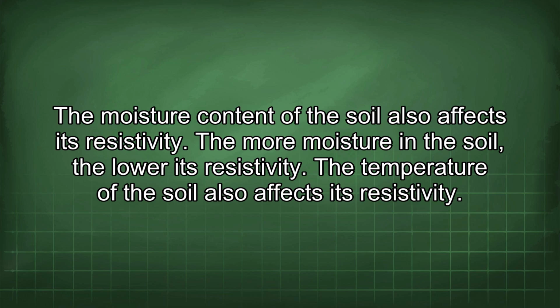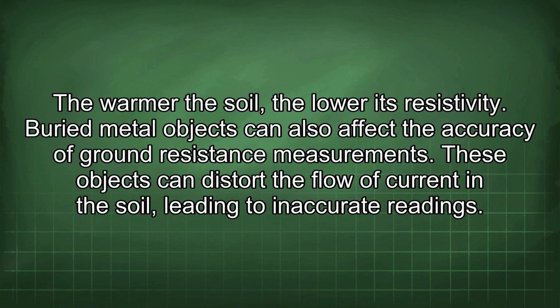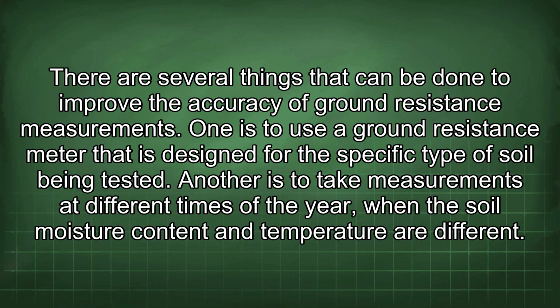The temperature of the soil also affects its resistivity. The warmer the soil, the lower its resistivity. Buried metal objects can also affect the accuracy of ground resistance measurements. These objects can distort the flow of current in the soil, leading to inaccurate readings. There are several things that can be done to improve the accuracy of ground resistance measurements.